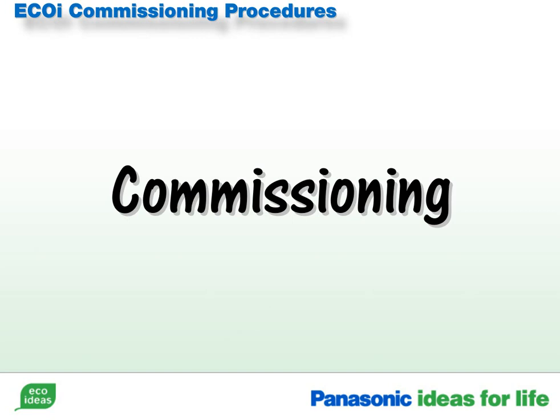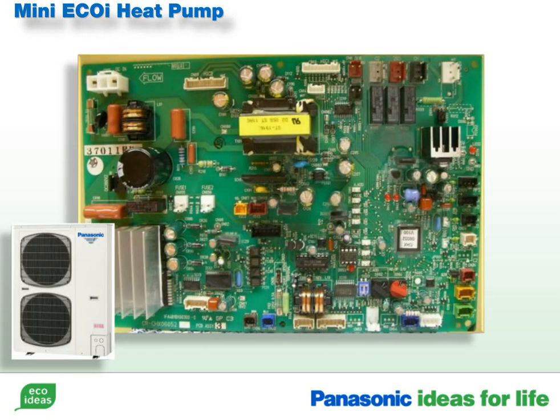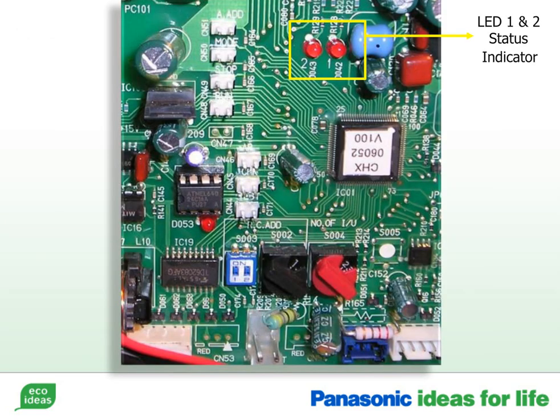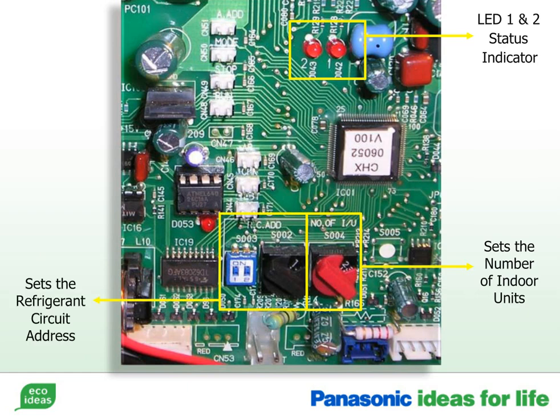Commissioning ECOi systems. Let's take a look at the U/LE Mini ECOi mainboard. LEDs 1 and 2 are used as the unit status indicator. If a system error is present, it will display the error code. The red dial labeled S004 sets the number of indoor units that are connected to the outdoor unit. The black dial labeled S002 is used to set the refrigerant circuit number. This allows a central controller or a servicer to differentiate between multiple ECOi systems in one location.